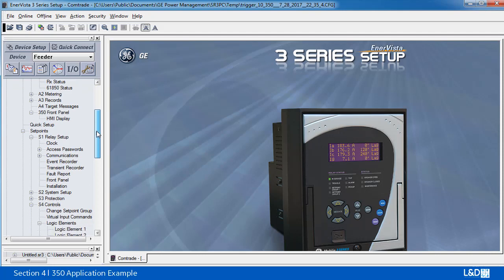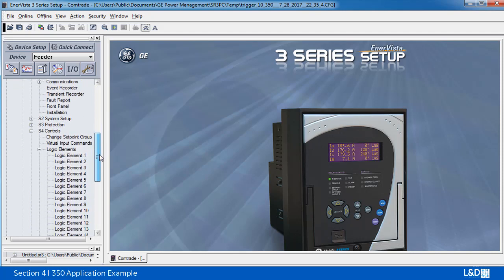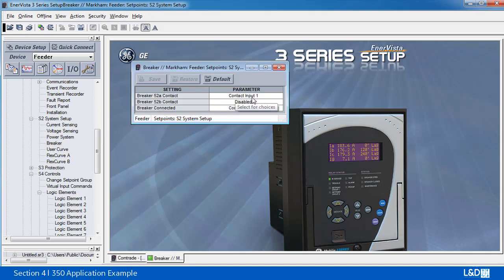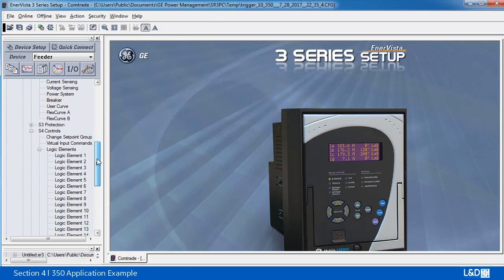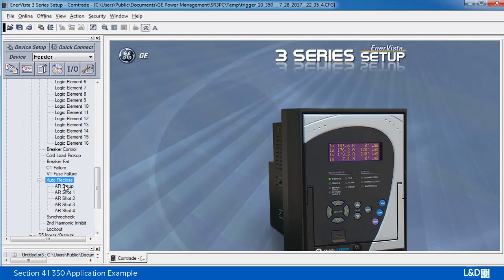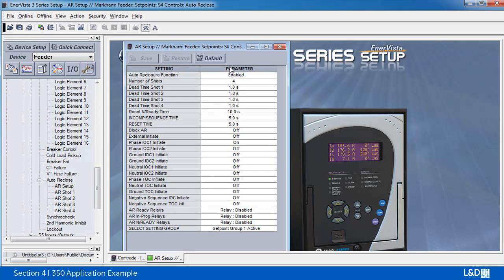Then in the 3 series setup software, we need to configure the system breaker first. We're going to use contact input 1 to simulate breaker close and open. We're not using breaker 52B in this exercise. Then we need to configure the auto-reclose. In this auto-reclose, we configured 4 shots, and for simplicity, we used 1 second dead time for each shot.